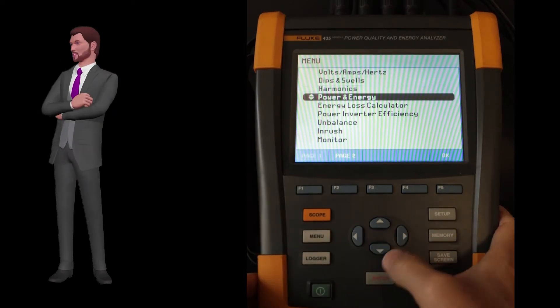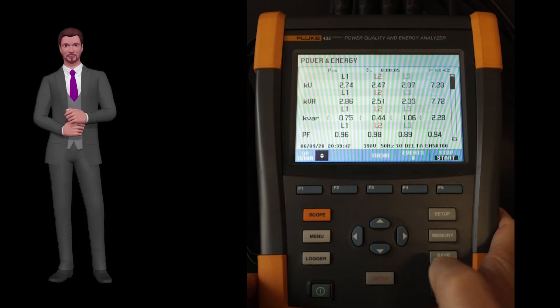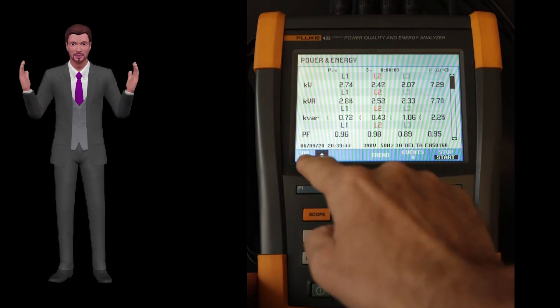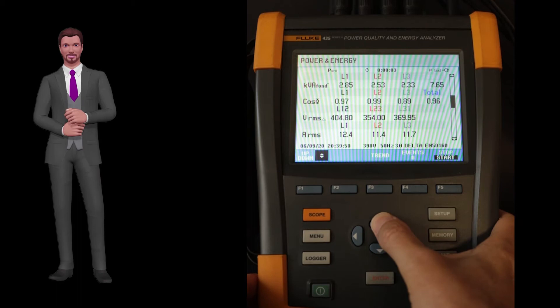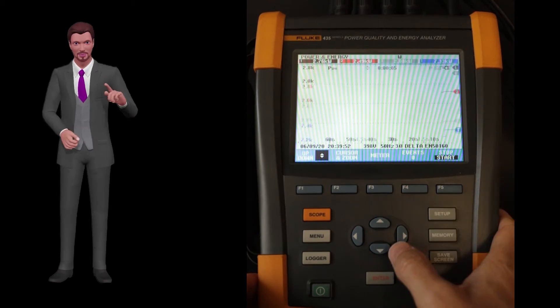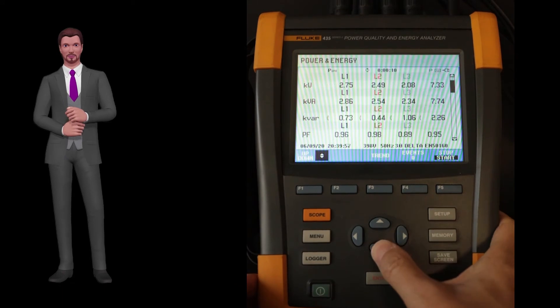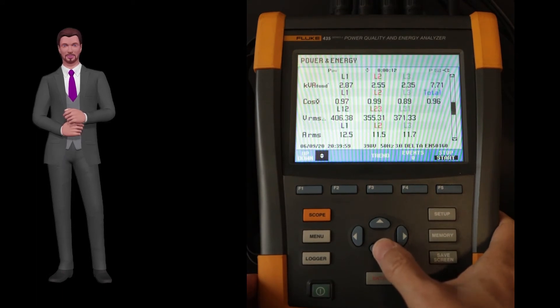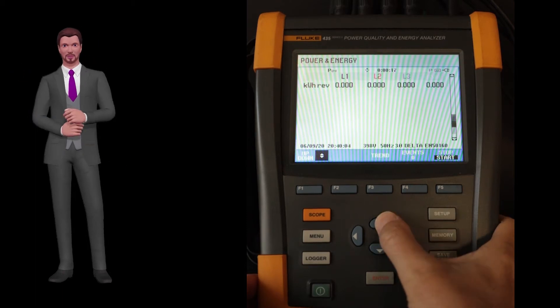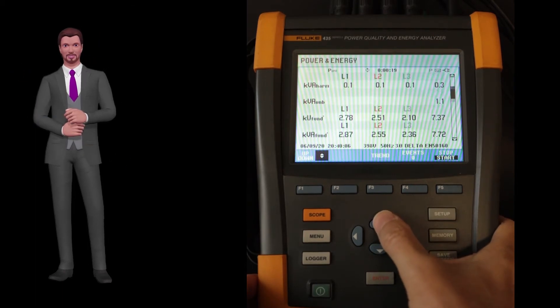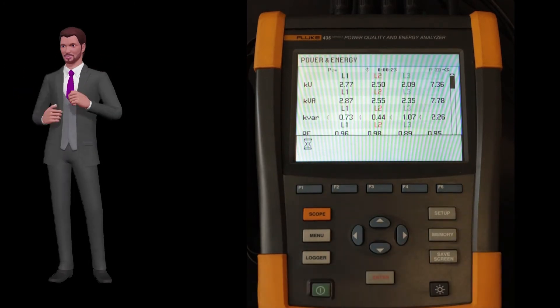The power and energy function allows us to measure and record parameters such as active, reactive, and apparent powers, power factor, harmonic power, power associated with unbalances, fundamental power, displacement factor or cos phi, voltages and currents, and active, apparent, and reactive energies. You will also be able to measure and record the active energy in the direction of the load and the energy reinjected into the grid. As you can see, it is a very complete function to perform energy efficiency audits.